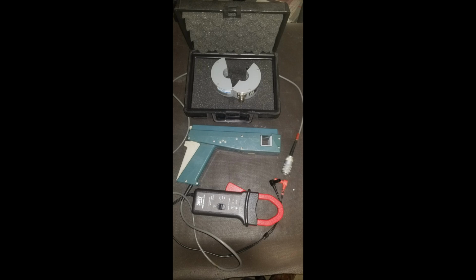Another type of oscilloscope probe that can be used to look at power line waveforms is a clamp-on current probe. Those probes do not require direct physical contact with energized circuits; they measure through insulation. However, they have disadvantages in that they are sometimes difficult to fit where you want to get the measurement, and they measure only through a single conductor. In addition, some of them require amplifiers, so that's one more thing to carry. But in certain applications, they will actually be easier to use than other types of probes because you won't need physical contact with energized circuits.